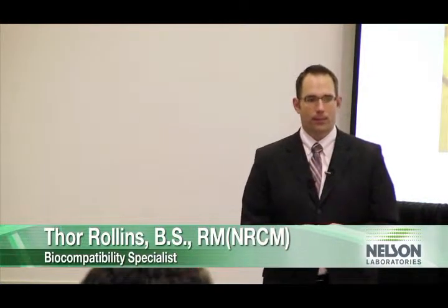Okay? So a lot of device manufacturers are going to be ISO 10993 compliant. If you can find something that's ISO 10993 compliant, then that means they've done cytotox and probably sensitization, and done some more testing to give you an idea. But if you don't know, like I said, you can send a list to me. I'm more than happy to go through it and let you know we've seen that problem with this one before, we've seen it with this one. We have a really good database at Nelson of problems we've seen in materials being passed. Did that answer your question? Any other questions?